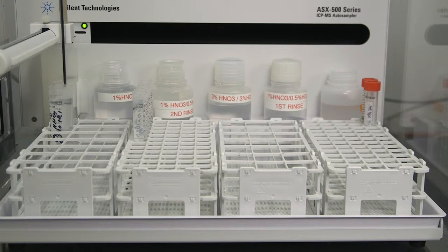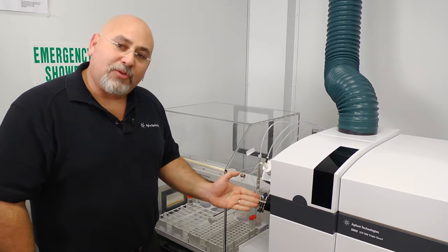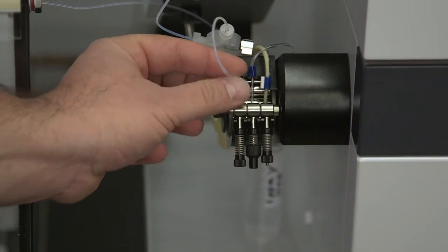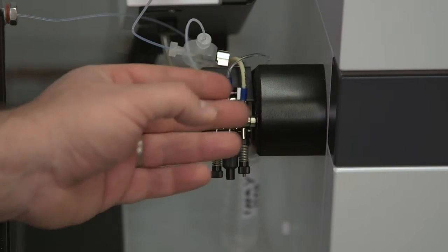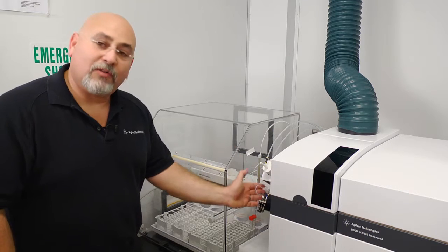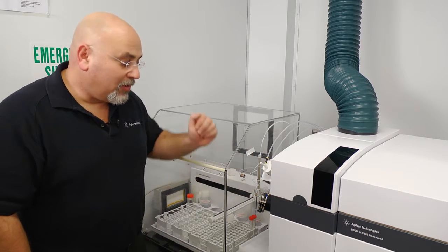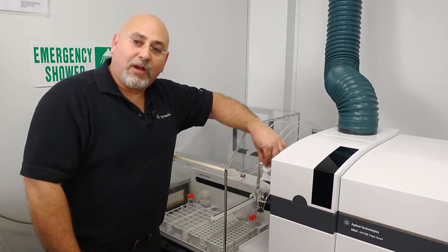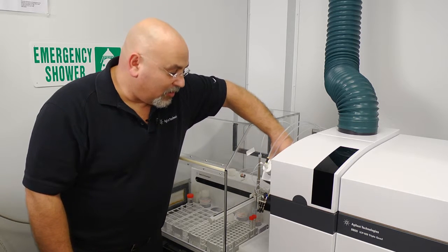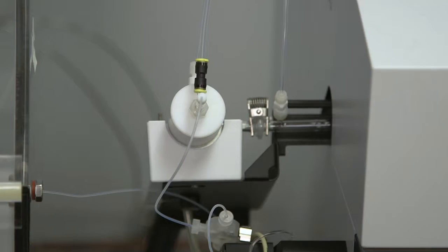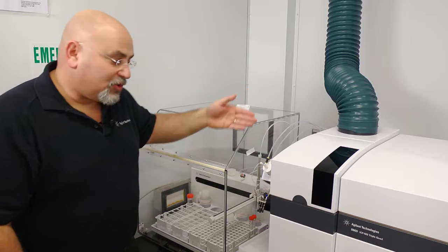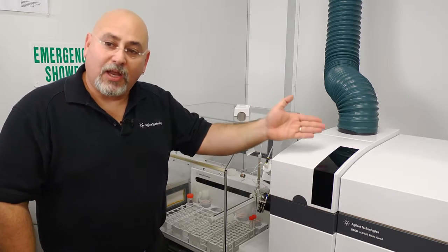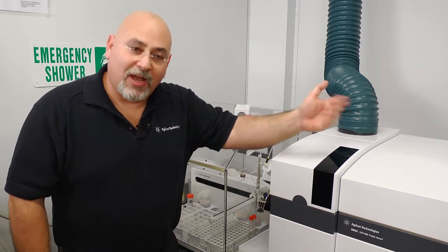Samples are typically in an autosampler, which goes through the samples being taken for analysis. We are using a 3-position peristaltic pump. The first position is for the sample uptake. The second position is for the internal standard, while the third position is for evacuation of the waste. The sample is then carried through a nebulizer. This is a low-flow concentric nebulizer, which nebulizes the sample into a Scott double pass spray chamber. The small droplets are then carried into the torch and eventually ionized in the plasma.